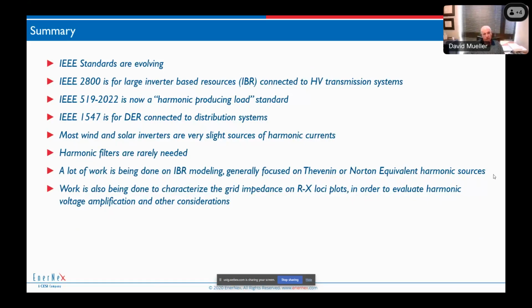But it's the only harmonic voltage standard that we have, and so it's still significant in our realm for harmonic voltages. In 1547, we talked about whether we ought to extend the harmonics beyond the 50th harmonic, because we're seeing some places where the higher frequency switching is causing issues. We decided not to do so. Too much trouble testing that, not considered enough of a common problem yet.